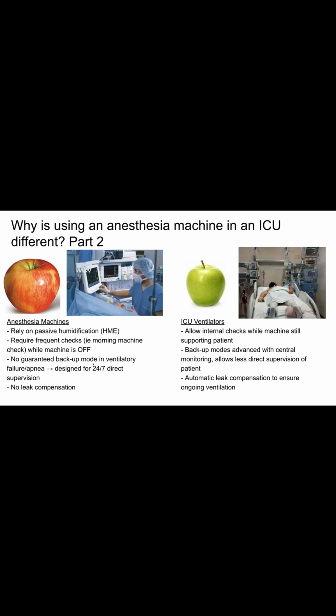And also importantly, there's no leak compensation. So if you have a leak in your circuit, you will empty your bellows and not ventilate your patient. Alarms should sound, but again, it relies on you being close by.